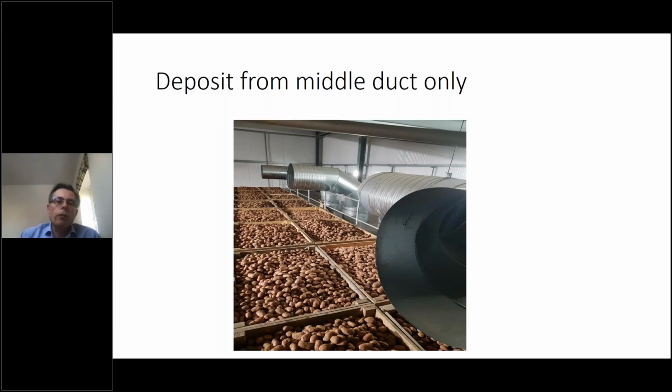On the older fridge units, where we have no inverters, we moved to pulsing during the application and just after. And again, we had no further deposits. So those were the two stores that gave deposits this year, and I think very much down to, in many ways, the fan speeds we were running. Next slide, please.